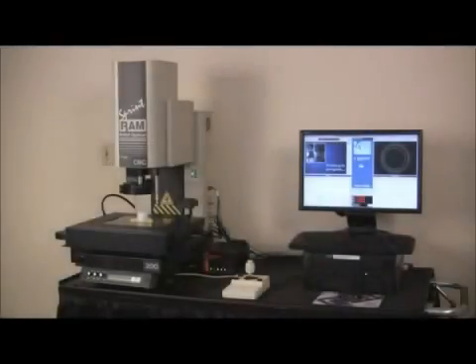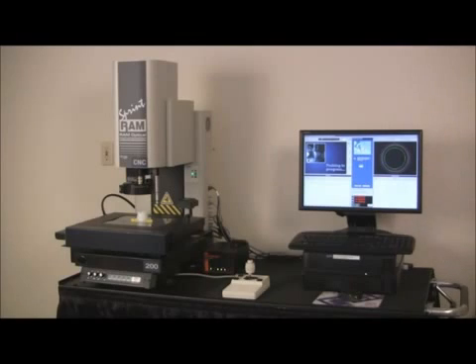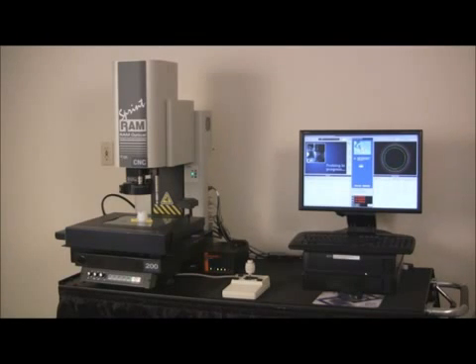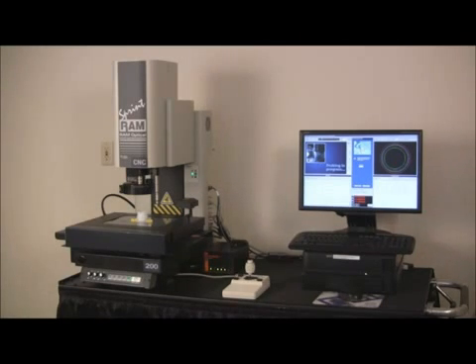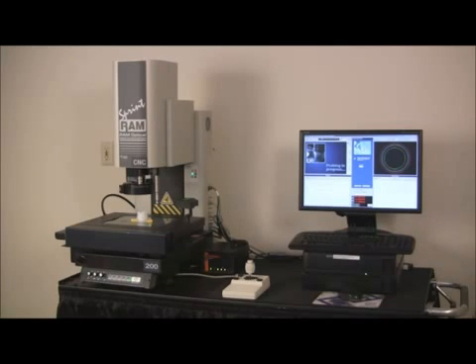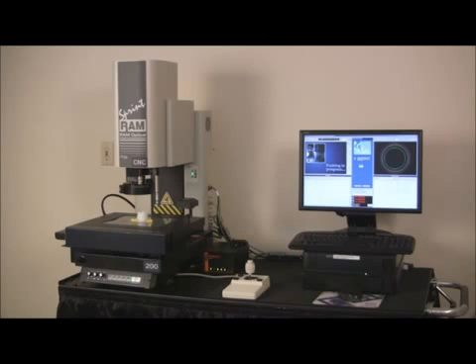Okay what we've done I removed the bottle in the horizontal position and I cut the neck off one of the other bottles. This machine only has six inches of travel in the z-axis and the length of the bottle was 9.15 so certainly we couldn't measure it standing up. Now we do have machines with a 12 inch z-axis where we can accommodate the bottle as it sits.